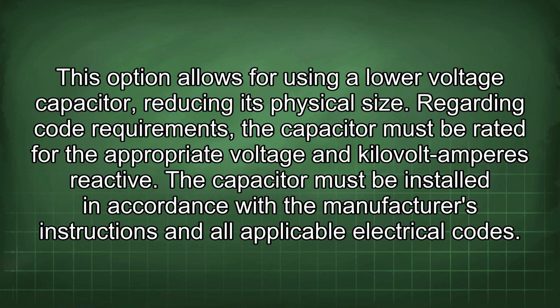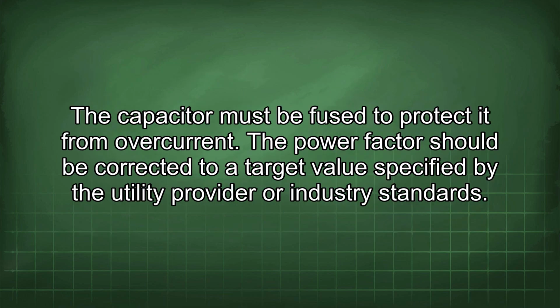Regarding code requirements, the capacitor must be rated for the appropriate voltage and kilovolt amperes reactive. The capacitor must be installed in accordance with the manufacturer's instructions and all applicable electrical codes. The capacitor must be fused to protect it from overcurrent. The power factor should be corrected to a target value specified by the utility provider or industry standards.